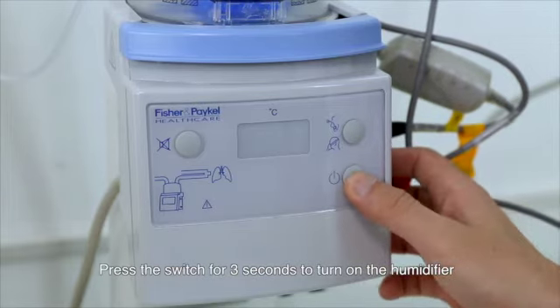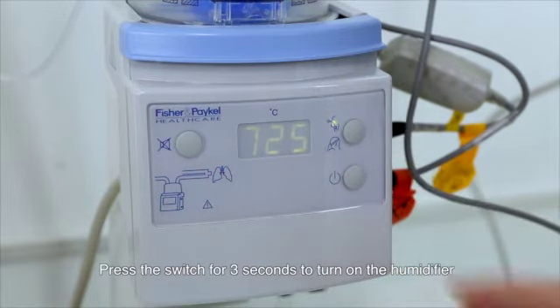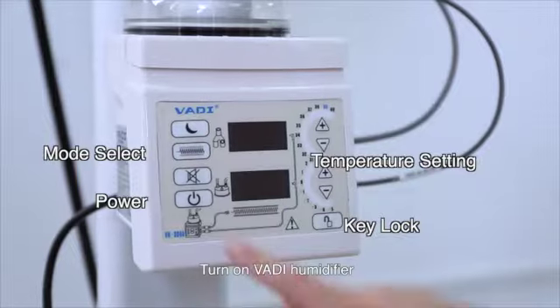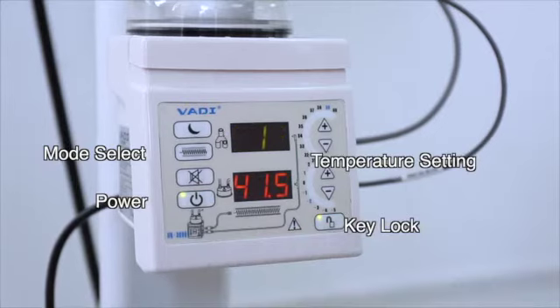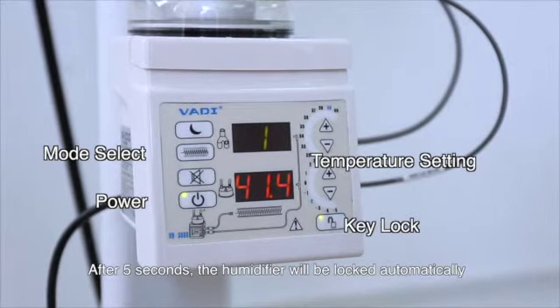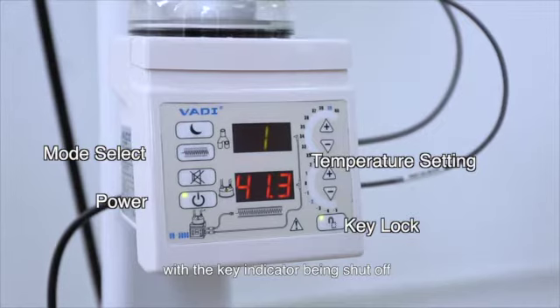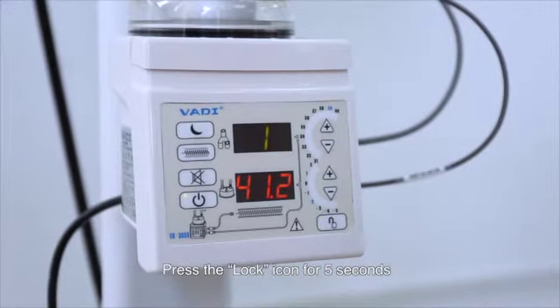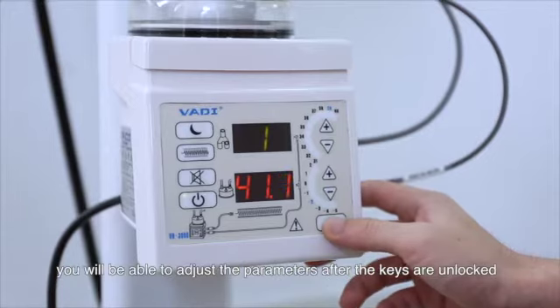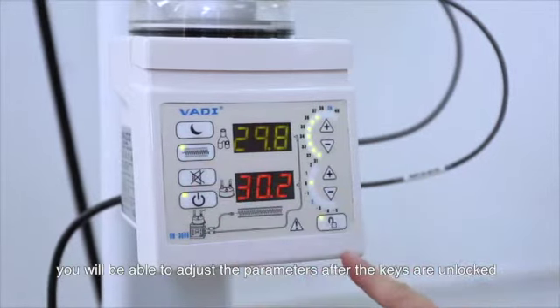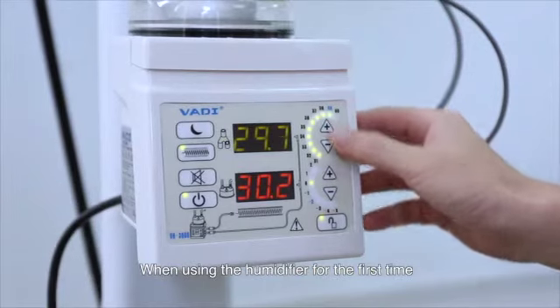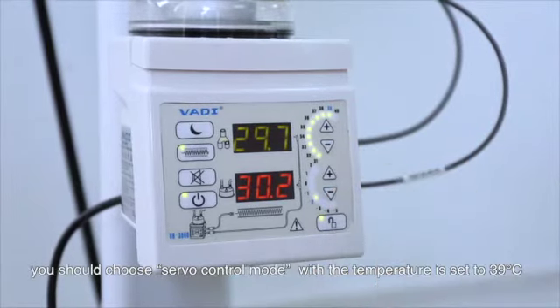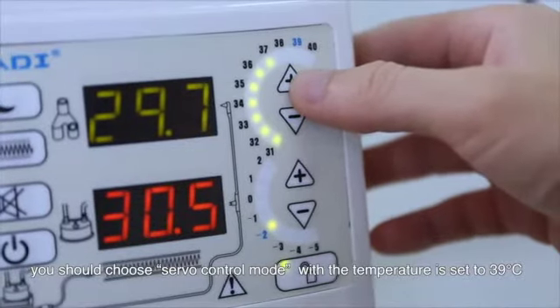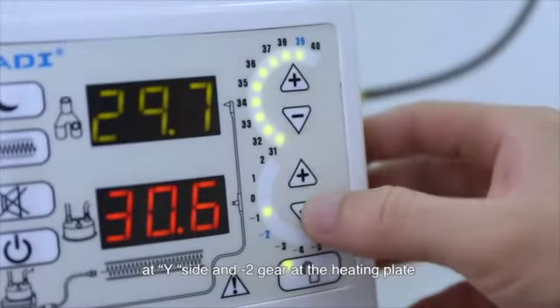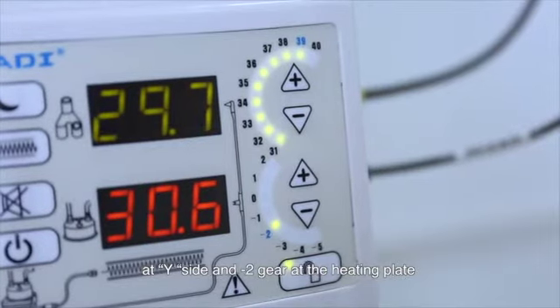Press the switch for 3 seconds to turn on the humidifier. Turn on the VADI humidifier. After 5 seconds, the humidifier will be locked automatically with a key indicator being shut off. Press the lock icon for 5 seconds. You will be able to adjust the parameters after the keys are unlocked. When using the humidifier for the first time, you should choose servo control mode, where the temperature is set to 39 degrees at the Y side and -2 gear at the heating plate.